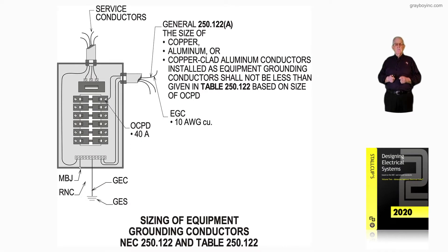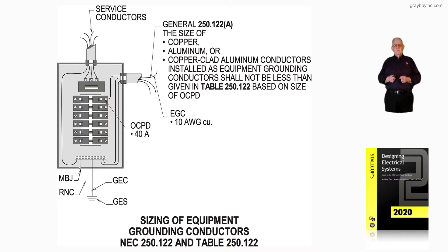This illustration deals with the sizing of equipment grounding conductors in accordance with NEC 250.122 and Table 250.122. This deals with Section 250.122 and Table 250.122 when we're selecting and sizing an equipment grounding conductor based upon the size of the overcurrent device and other issues that may develop.